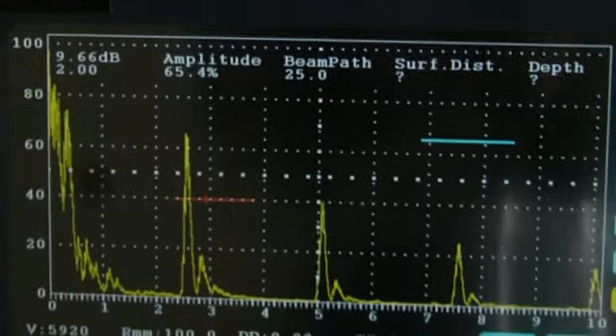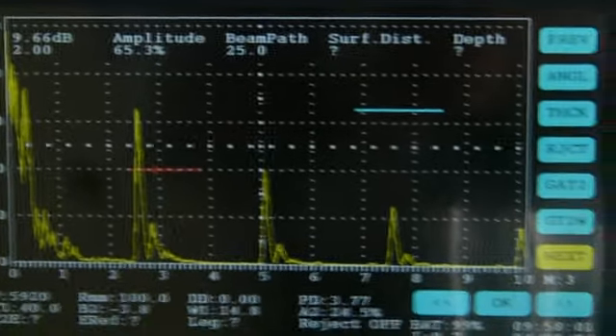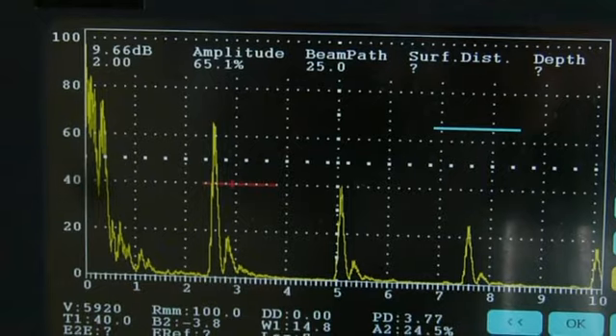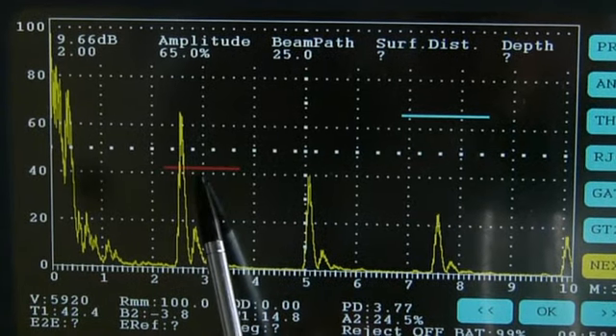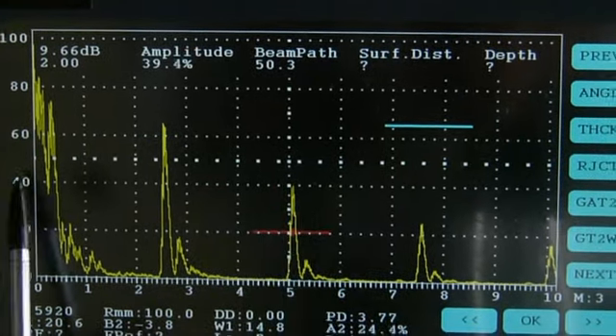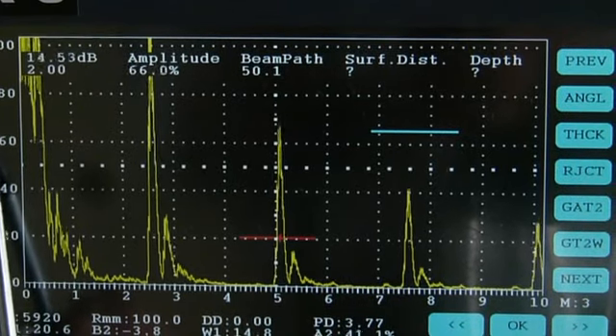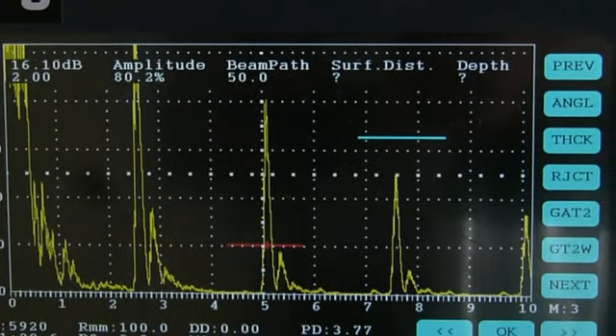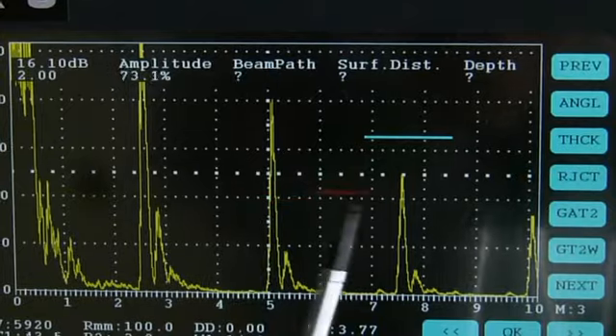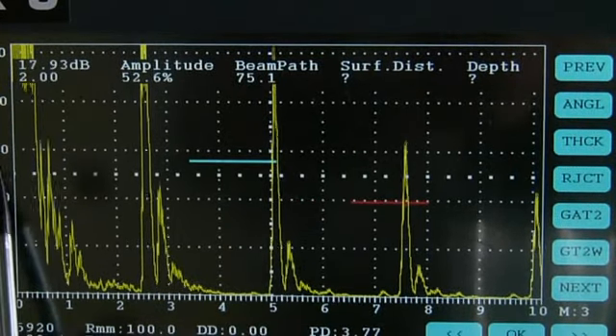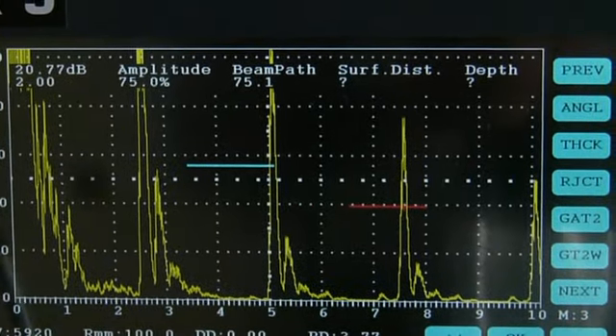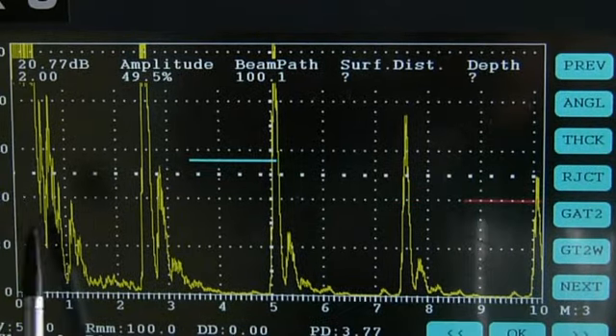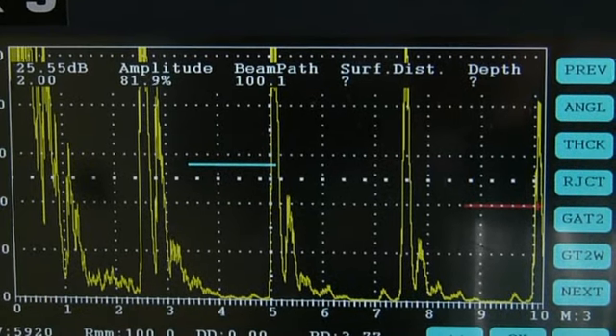So you have these 4 echoes being presented. The first echo appears at 25. If I move the gate to the second one, it should read 50 millimeter. The third one is supposed to be at 75, and the fourth one at 100. So this sets up a range of 100 millimeter.